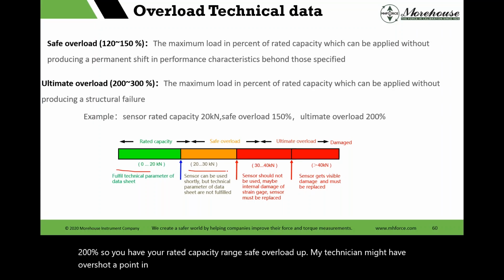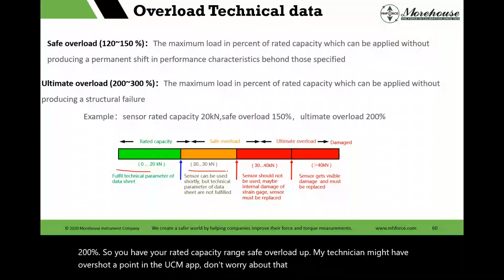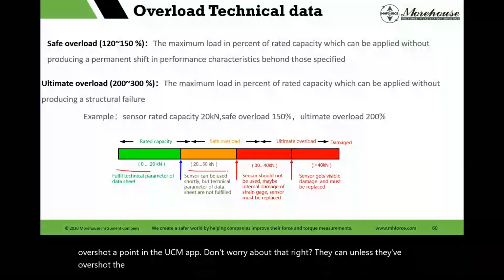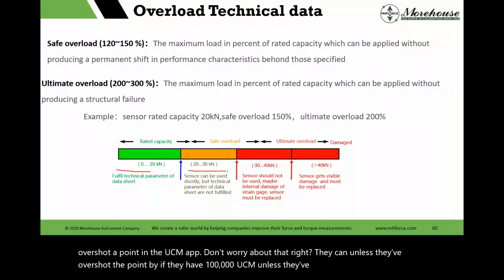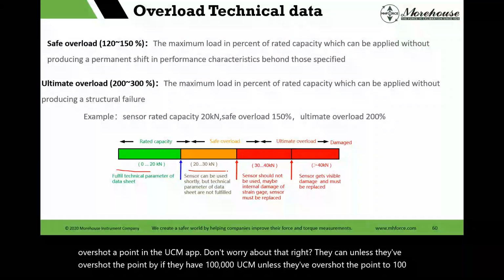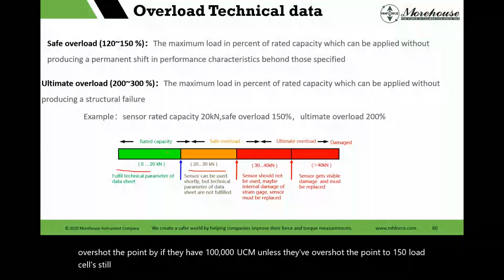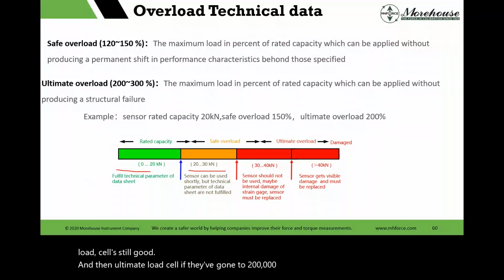Don't worry about that, right? They can, unless they've overshot the point. If they have 100,000 UCM, unless they've overshot the point to 150, the load cell's still good. And then ultimate load cell, if they've gone to 200,000, the machine's probably coming apart with some other things.